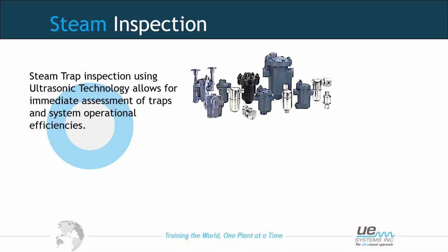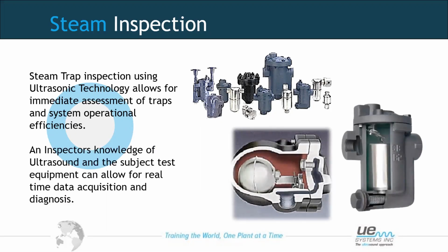So with steam trap inspections, using ultrasound technology will allow us to have an immediate assessment of the steam trap operation itself and its efficiencies. An inspector's knowledge of the subject area will also help with understanding the condition of these traps. There are many, many different types of traps, and understanding how they operate will help us understand how they are working. So is it an on-off trap? Is it a continuous flow trap? Depending on the type of trap will also depend on how it sounds. And again, it's using those senses to help guide our way through.